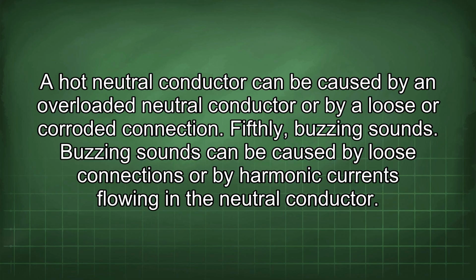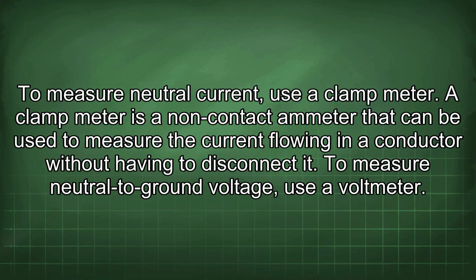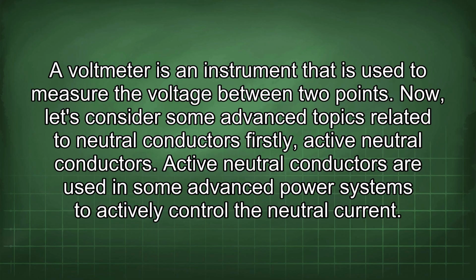A hot neutral conductor can be caused by an overloaded neutral conductor or by a loose or corroded connection. Fifthly, buzzing sounds. Buzzing sounds can be caused by loose connections or by harmonic currents flowing in the neutral conductor. To measure neutral current, use a clamp meter. A clamp meter is a non-contact ammeter that can be used to measure the current flowing in a conductor without having to disconnect it. To measure neutral to ground voltage, use a voltmeter. A voltmeter is an instrument that is used to measure the voltage between 2 points.